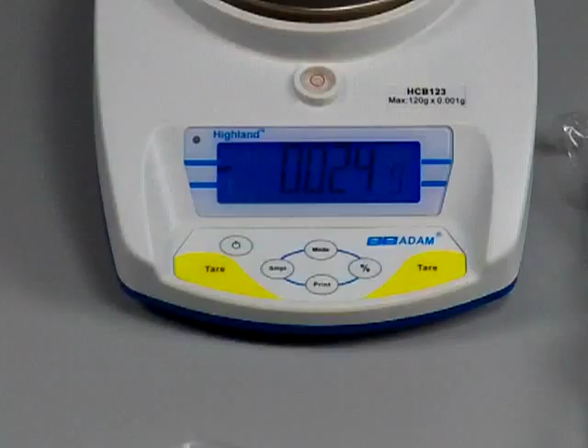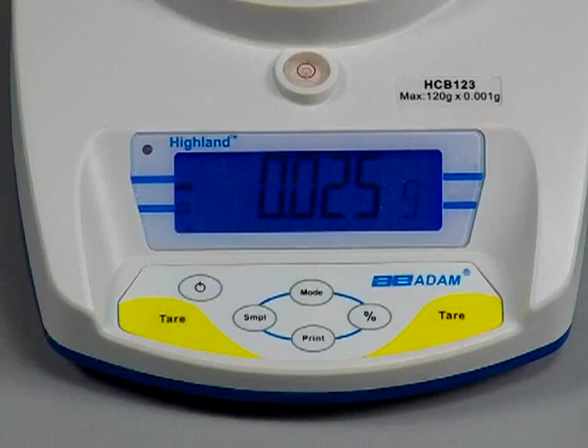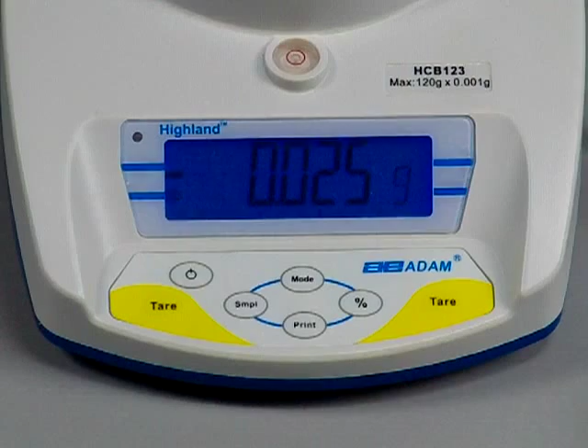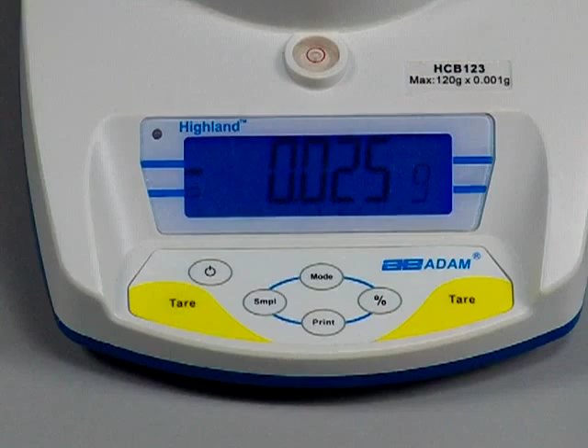The scale also features, we're going to go over these keys now. So we have 2 tare keys, both right and left, which is real nice and handy to have, and we have a mode key. This mode key allows you to scroll through the available weigh modes, and this scale has just about every mode imaginable, even newtons. And a real nice feature about this scale is, if you turn the scale off, we'll say in ounces, you shut the scale off, when you power it up, it will come back in ounces.